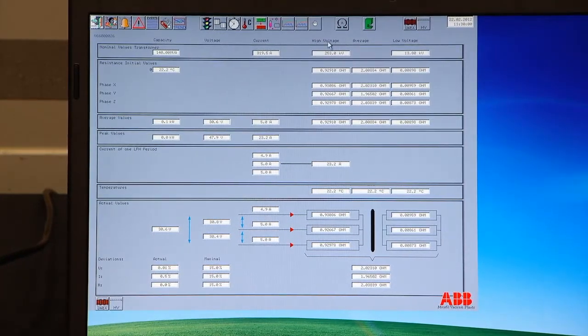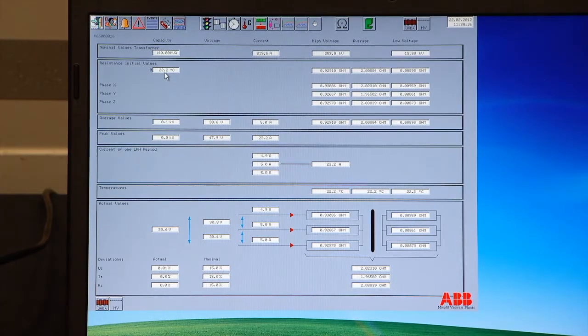Since we did a high voltage measurement, we have the resistance from the high voltage winding measured, 930 milliohms approximately, and you have the average of those 3. We have now the average and we have the high voltage. The low voltage is then calculated. This is not measured, that's calculated based on the average and the high voltage and the transformer conversion ratio. This is now matched to our initial temperature, 22.2 degrees. Initial measurement is done. We are ready to go into heating.